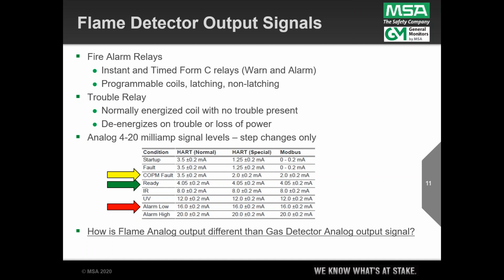The fourth type of output is the analog 4 to 20 milliamp signal, and this is a step change only signal level, and I put some arrows here. So green is good, and that correlates to the device's green LED, and that means it's at 4 milliamps. And if it would have a dirty window, or what we call a COPM fault, then it would drop down to 3.5 milliamps, although we have options in the second and third column at 2 milliamps. Some clients have a standard analog level they like to use to indicate a specific type of fault, and we can do that a little more granularly with those levels. And then we have the alarm level, in this case at 16 milliamps, the instantaneous fire.